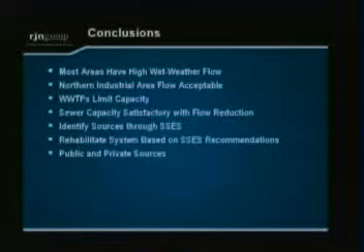So how do you do that? The next step is the sanitary sewer evaluation study. Basically, we're looking for where the flow is coming in, specifically finding defects in your manholes, in your sewers, and whether it's coming from the homes, identifying that, and then moving forward and eliminating those sources. One thing I just want to touch on, because you're going to hear more of this over the next few months, is that you have both public and private sources. I want to show you this pie chart here.